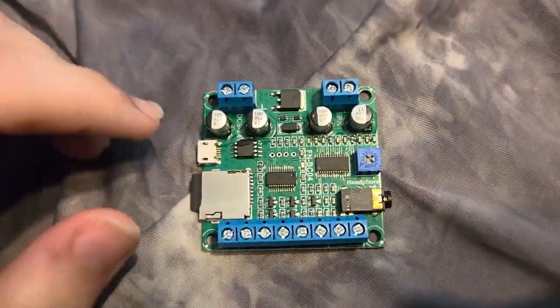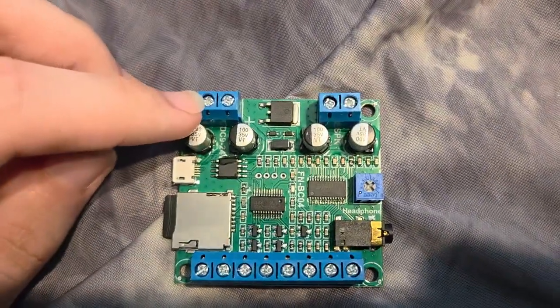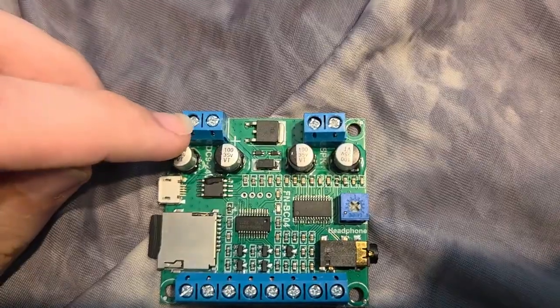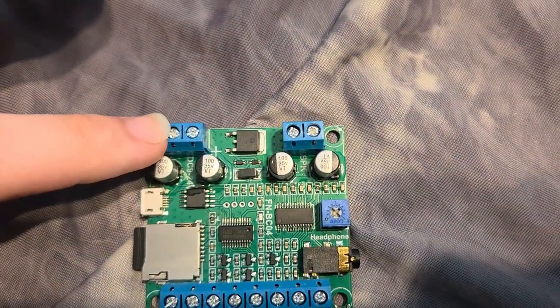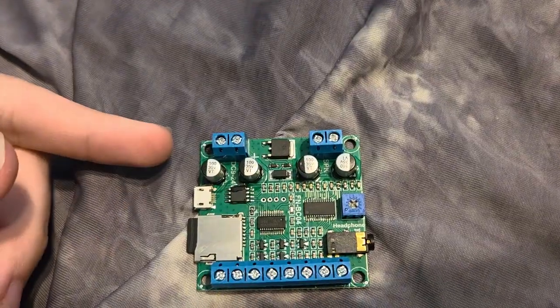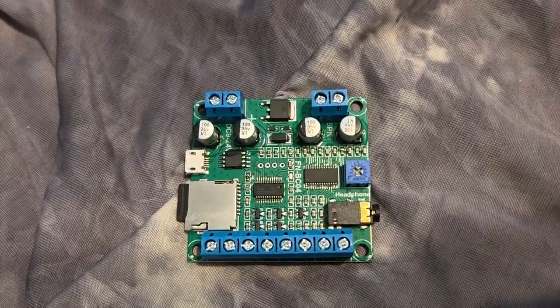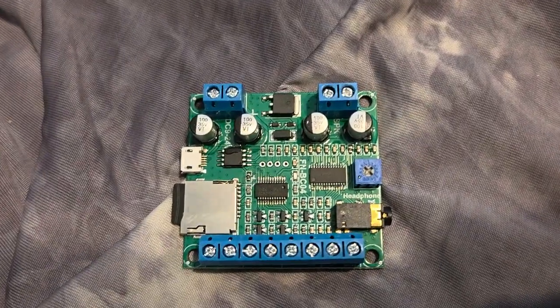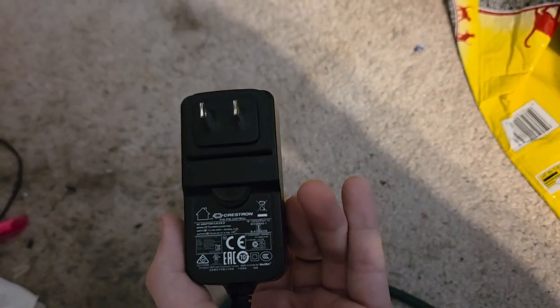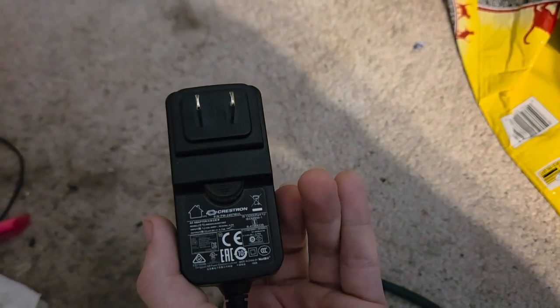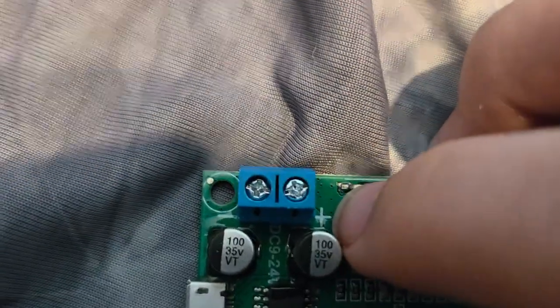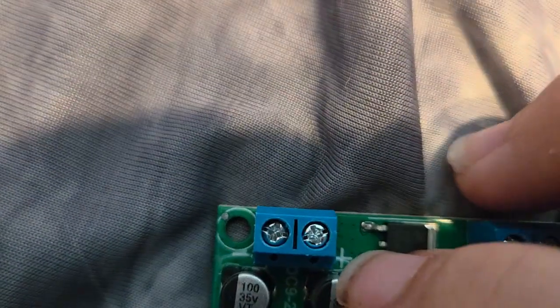On the top left, here you have your power input. This is where you would supply power to this entire device. You want anywhere from 9 volts to 24 volts. For this, you could just use either your panel's auxiliary power supply, or if your panel's auxiliary power supply doesn't supply enough milliamps, then you could just take a power supply that you plug into your wall. For your input, left is negative and right is positive. As you can see here, there's a minus sign there and a positive sign there.